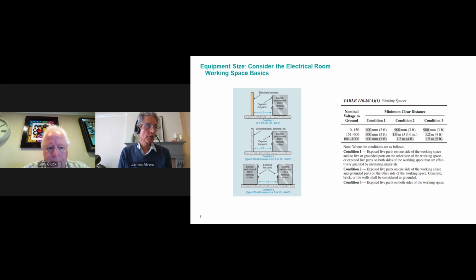Some quick basics on access. Of course, access is needed for maintenance, et cetera. But one of the code's primary concerns is access to provide egress in the area in the event of an arc flash incident. Minimum doorways are typically 24 inches wide by 6.5 feet high. But bigger doors are always better. Remember, you've got to maintain the equipment. You may need to add equipment or remove equipment. So you want to think about those things.